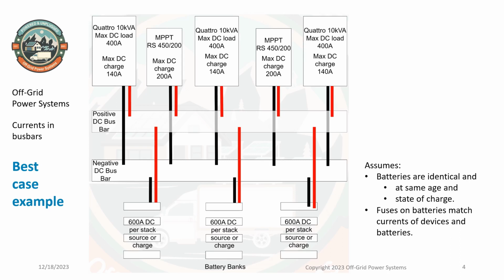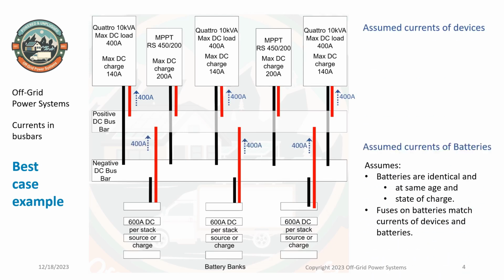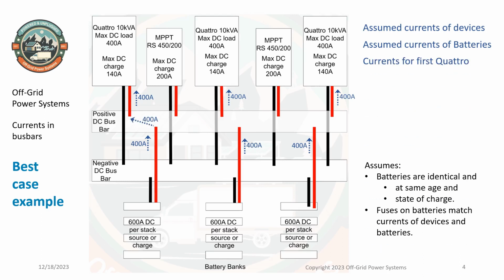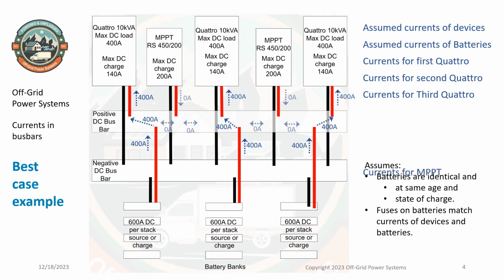Now let's consider a different placement of the loads and sources of current. Same devices as before, and let's see what happens if we place them in different places. The Quattros have the same loads as before. The batteries supply the same currents as before. Starting from the left, the first Quattro is supplied by the leftmost battery. The middle Quattro is supplied by the middle battery, and the right Quattro is supplied by the right battery. The MPPTs are supplying no current, and this doesn't change any of the currents. Surprise! The maximum current on the bus is 400 amps, just by connecting the devices in different positions.